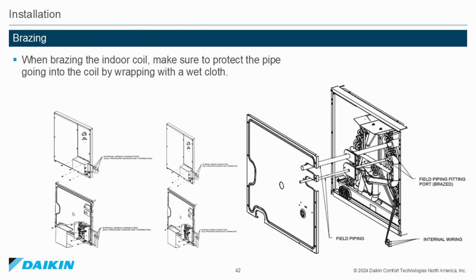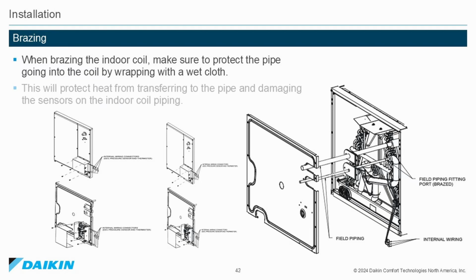Brazing. When brazing the indoor coil, make sure to protect the pipe going into the coil by wrapping it with a wet cloth. This will protect heat from transferring to the pipe and damaging the sensors on the indoor coil piping.